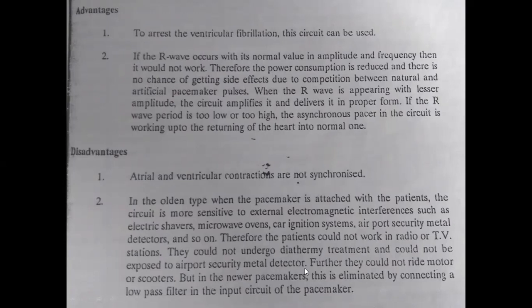Starting the motors or cars will also produce high impulses. That's why it also creates a pulse disturbance to the actual signal. But in the newer pacemakers, this is eliminated by connecting a low pass filter in the input circuit of the pacemaker.